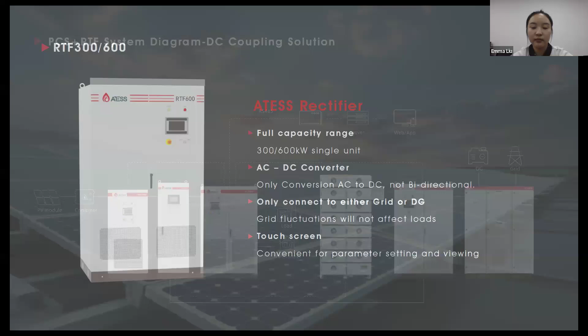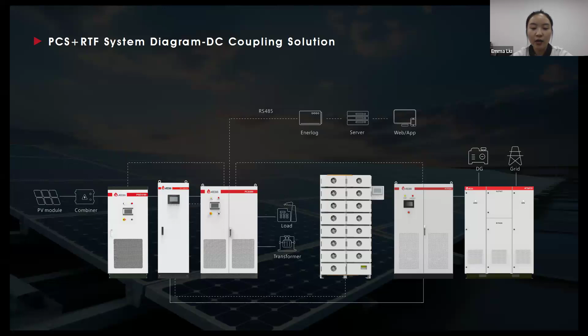And the battery and the PV power are both DC powers, which are also coupled to the main DC bus below. After the DC cabinet is combined, it flows to the PCS and is converted into AC power output to the load. No matter how unstable the AC power is, the PCS will always remain in off-grid working mode, no longer switching between on and off, and no longer having switching time. The battery is always online.